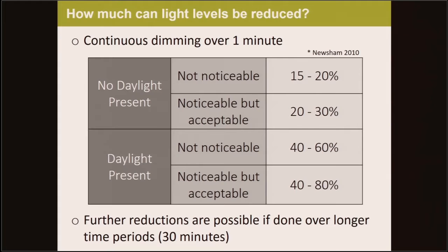Lab and field studies have shown that significant reductions can be made to light levels and the corresponding electric power demand. If daylight is not present, light levels can be reduced by 15 to 20% from recommended levels without occupants even noticing, and between 20 and 30% was considered tolerable. If daylight is present, the reduction can be even greater — up to 40 to 60% without occupants noticing, and up to 80% was tolerable. Note that these are with respect to recommended light levels, so if levels are actually higher, even more dimming is possible. This assumes dimming occurs continuously over some short period of time, for example one minute. If dimming happens instantaneously or stepped, the reduction is much more noticeable and that's not recommended. Also, if the dimming took place over a long period of time, up to 30 minutes, like in a demand-response scenario, then further reductions were obtainable.